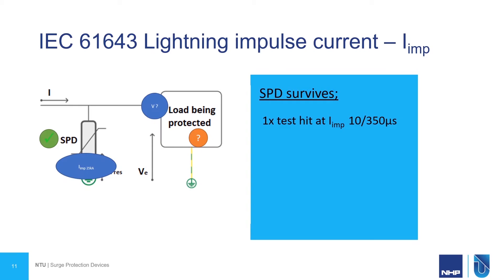IIMP is the lightning impulse current. Again, this is the largest test current that an SPD can survive one time. The difference here is that this is with the 10 over 350 microsecond waveform, so this is for our Type 1 devices where we're protecting from lightning.